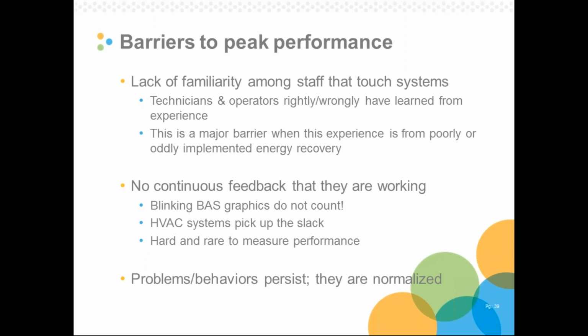Another major barrier is that there's no real continuous feedback from a staff perspective that ERVs are working. And I'll note here that blinking automation system graphics don't count. They're not necessarily reliable, and they don't really communicate to the operators and technicians what's actually happening. The other part of this is that while we could use energy recovery systems to downsize traditional equipment, in the systems that we studied, that isn't the case. So when ERVs aren't working, HVAC systems are picking up the slack. ERVs are energy efficiency technologies existing in the background. When they don't work right, the only consequence is more energy for heating and cooling. And this persists, especially if it exists from day one. There's no baseline to compare to.